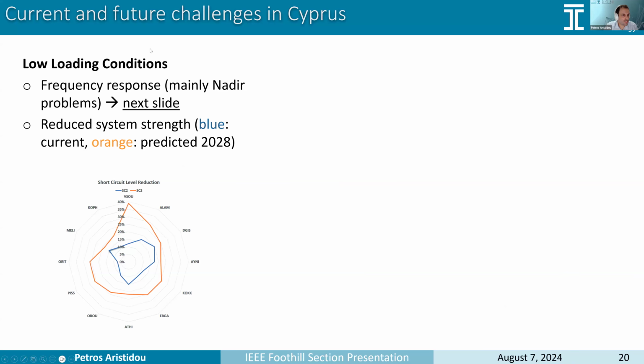First, if we check during low loading conditions, we have lots of problems related to the frequency response of the system. So a lot of frequency security problems, mainly with the nadir. Post-fault nadir, and we're going to see that in the next slide. And at the same time, we have lots of problems with the reduced system strength. This is the same figure I showed at the beginning of the presentation, where we can see that already we have a 20% reduction in fault levels in some substations, and in another 4 years, it's predicted that that would reach up to 40%.